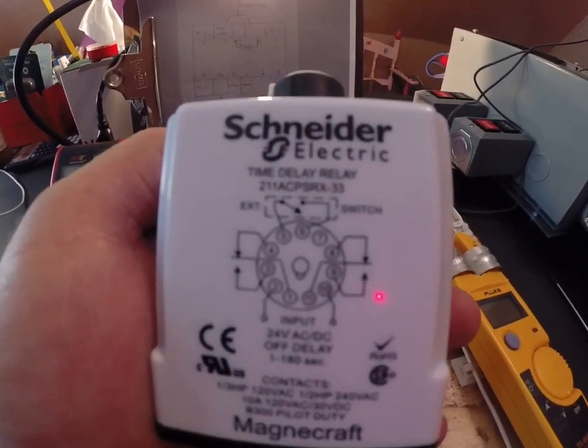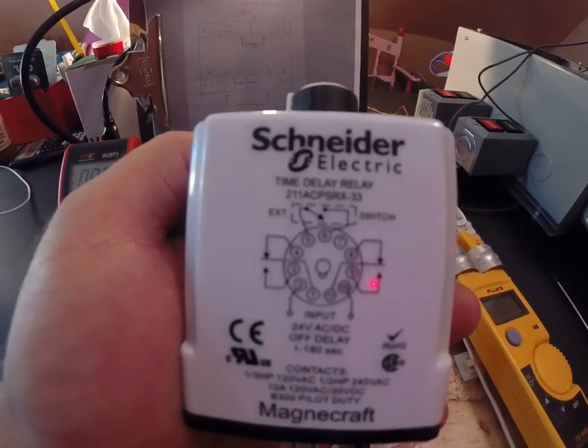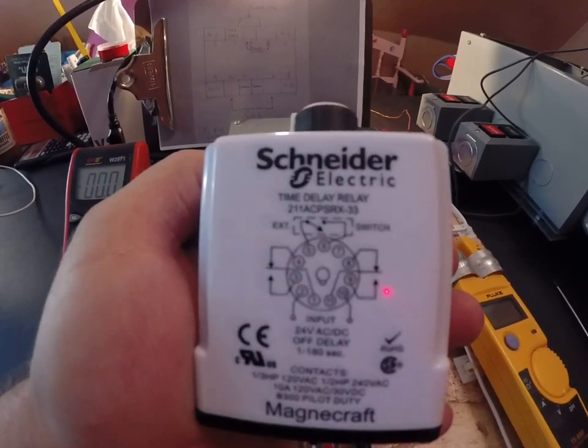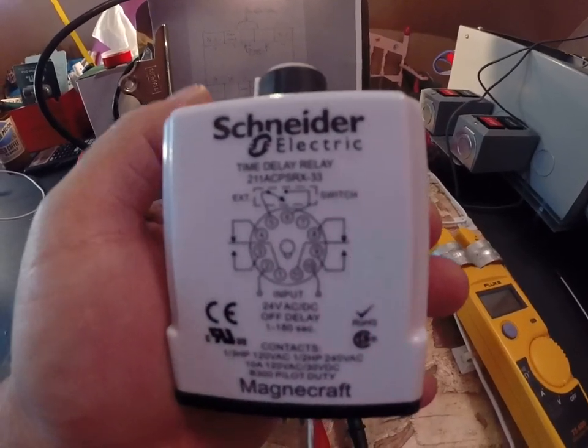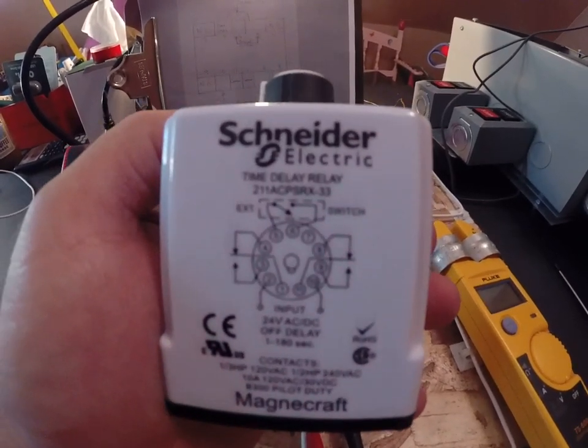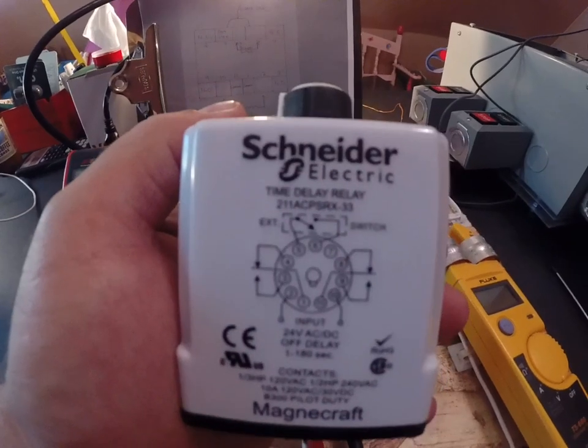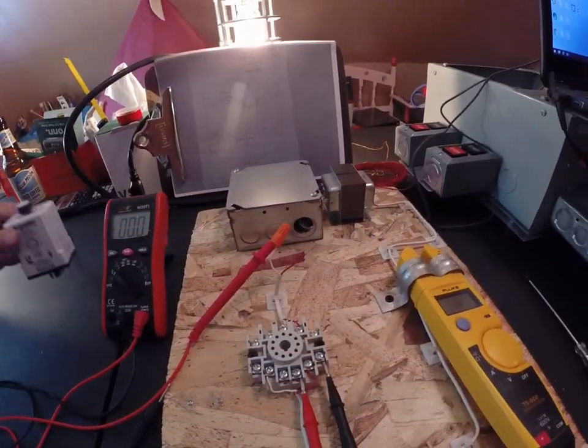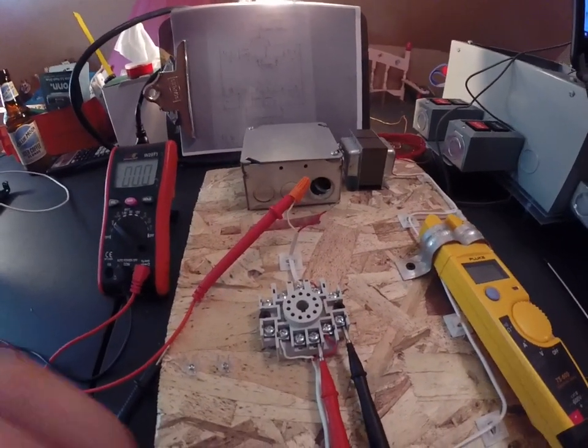At the top of the diagram, right above the circle, there's a trigger switch. So pretty neat. What most people don't understand is if you accidentally put voltage to that trigger switch, you'll likely fry and ruin the relay, ruin the switch, because there's actually a voltage present on that.